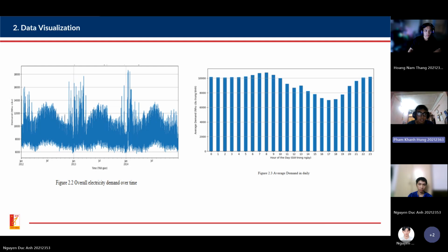the demand spikes and reaches its highest peak of the day at about 8 a.m. After the morning peak, demand begins to decline slowly, especially after 12 noon, and it reaches its lowest point of the day around 4 to 5 p.m. After 5 p.m., the demand increases sharply again and reaches its highest point around 9 p.m. to 11 p.m. This is the peak of the residential load.